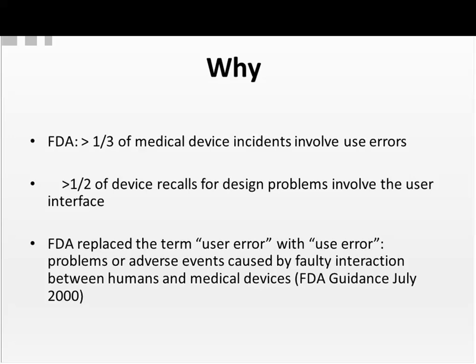The FDA, by studying recalls and other incidents in the field for medical devices, has concluded that 1/3 of medical device incidents involve use errors, as opposed to device problems and failures. Over 1/2 of the device recalls involve the user interface. So the FDA has concentrated on human factors in the last few years.